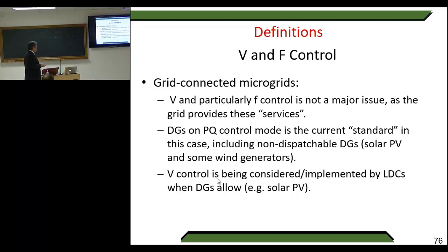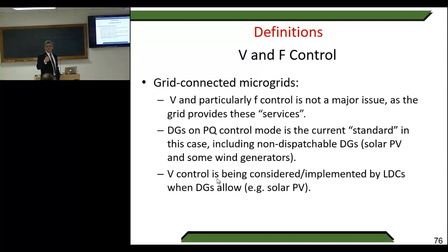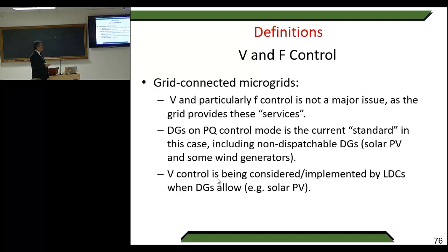In grid-connected microgrids, DGs in PQ control mode is the current standard, including non-dispatchable distributed generators like solar photovoltaic and some wind generators. You normally go to a PQ control with some power factor, try to move with MPPT at maximum power, and rely on the network to support this. The problem is that when you need to be isolated, you need a very clear strategy for islanding operation. Voltage control is also being considered, implemented by LDCs when DGs allow.